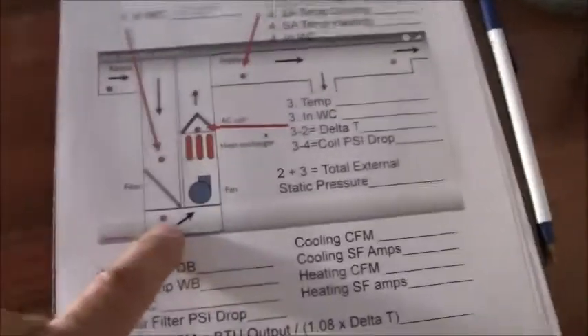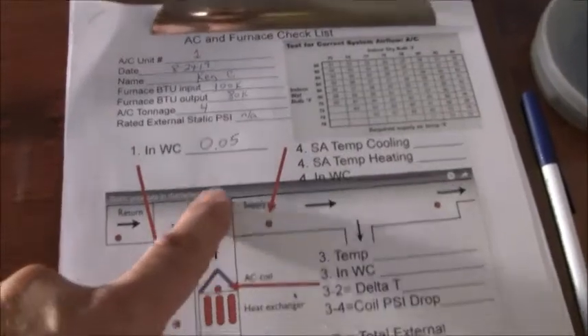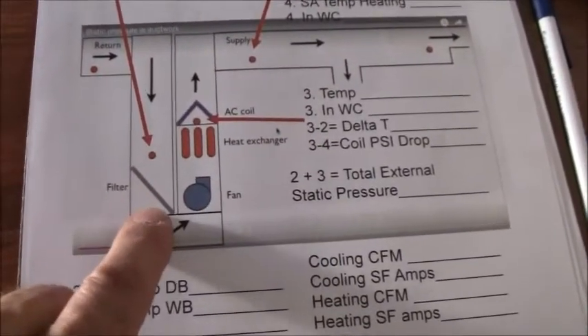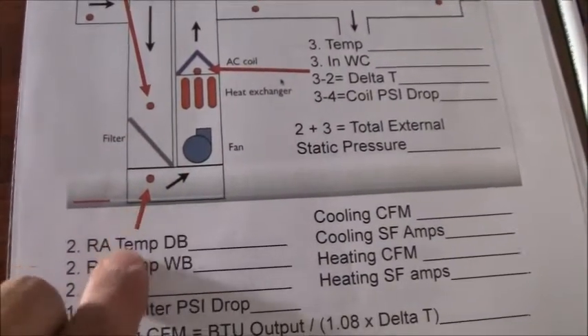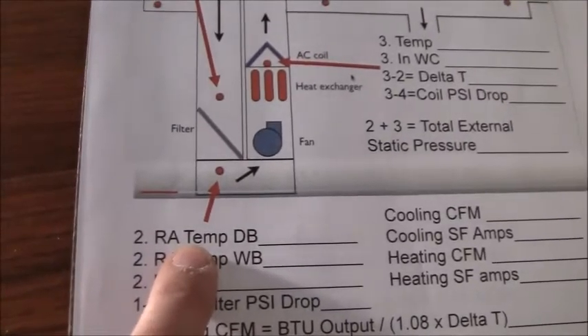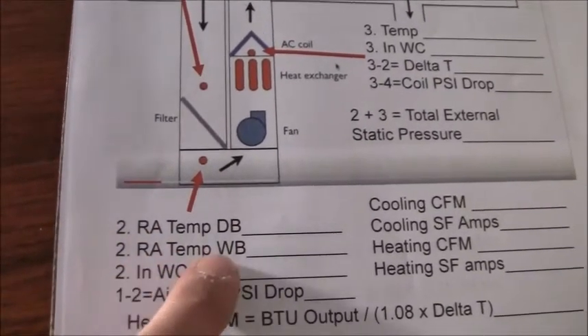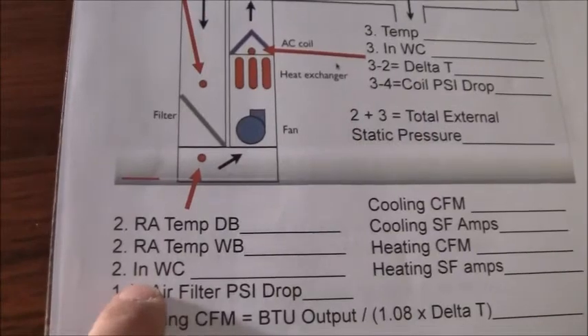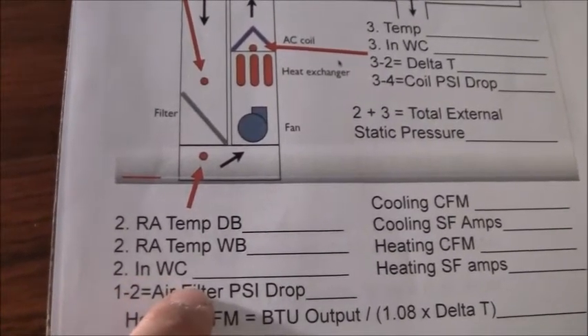The next one that we want, okay, so 0.05 right there. Then you have a filter, then there's the next point right there. We need to know what that is. And we'd like to get the return air temperature, dry bulb, wet bulb, and the inches of water column. So let's start with the inches of water column.